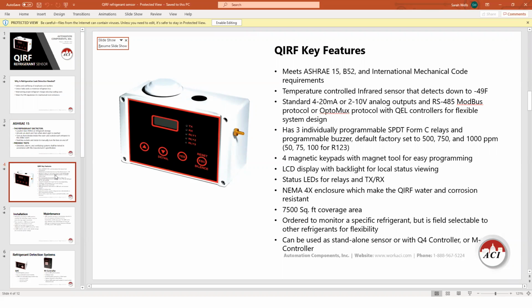Sometimes specifications are different, but standard is 500, 750, and 1,000 ppm, except for the R123, of course. And the magnetic keypad that comes with it, correct? Yep, there's a magnet tool that comes with the QIRF, and that's how it's programmed, just using the magnet tool. It doesn't have to be the same tool that comes with it. If it gets lost, you can just go to the hardware store and pick up one of those magnet tools that are used for picking tools up off the floor, that thing that mechanics use.